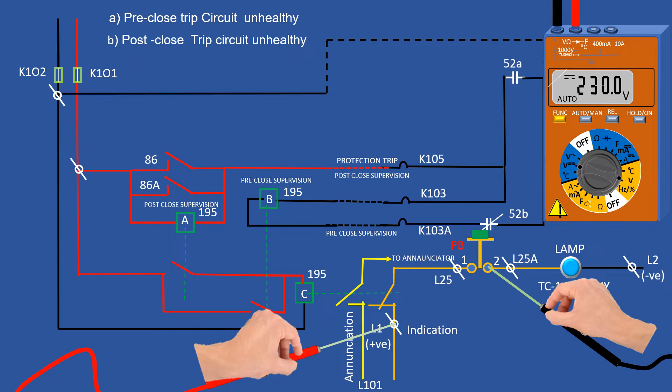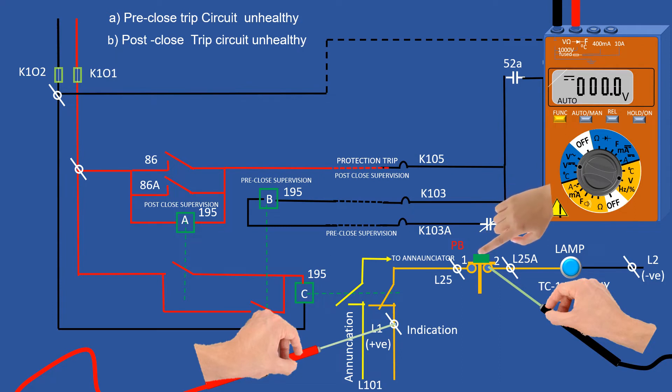Now keeping red lead at L1, black lead is placed at terminal two of the push button. Multimeter shows 230 volt DC, that is lamp is okay. Keeping red lead at L1 and black lead at two, press the push button and watch. If the multimeter reading is zero, then total circuit is okay.